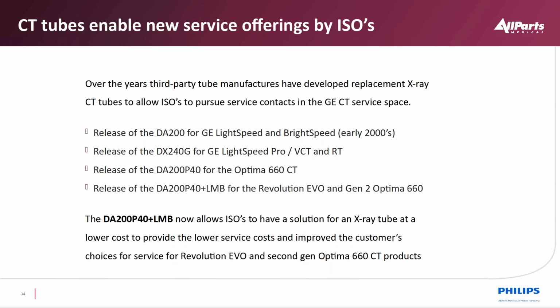Some of the things that we have with regards to GE is we have alternate glassware available at AllParts for that. Some of these examples are tubes. The Optima 540 is not shown on here, but that actually has a liquid bearing tube as well. GE and a lot of manufacturers have gone from metal ball bearings to liquid metal bearings. So that changed the technology and some of the parts leverage for some of these machines. So it's a newer technology for some of the GE scanners. It's been in other OEMs for a while. Okay.